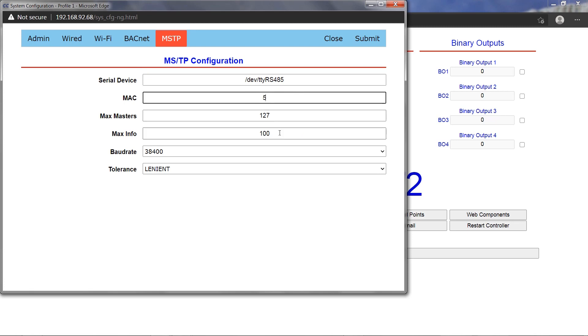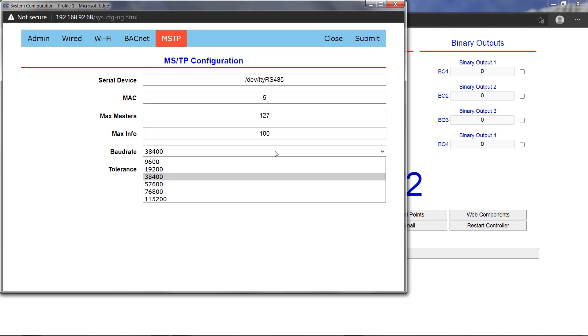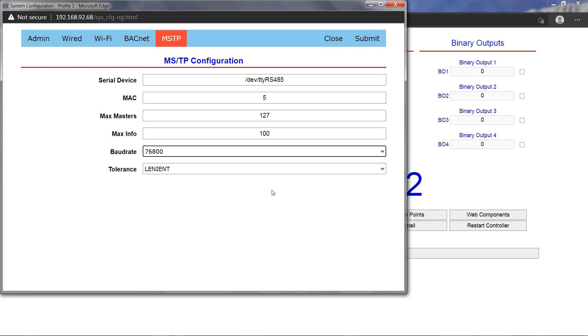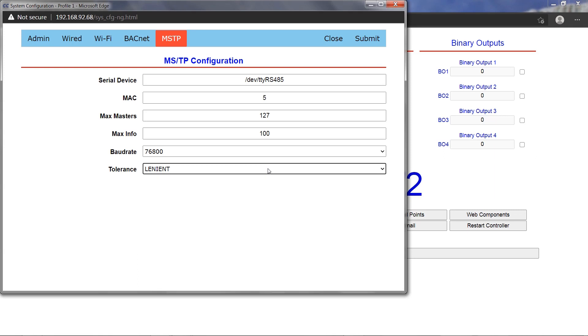The serial device field is pre-configured and does not need to be changed when the dongle is inserted into the USB port. The BASpy Edge MAC address can be set in the MAC field. The max master setting should be left at 127 unless configured otherwise on the BACnet MSTP network. Max info frames should be left at the default value of 100.